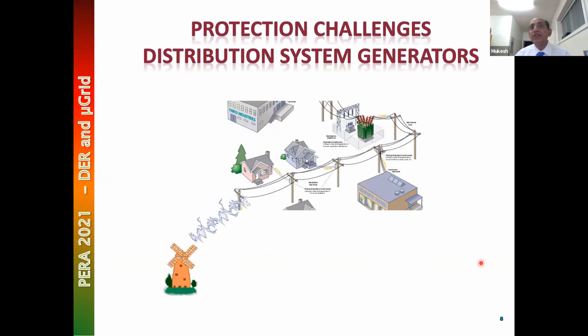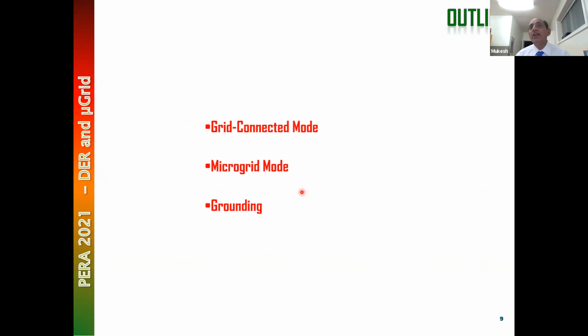So we have a distributed generation connected to a distribution system, and what kind of things is it going to do? First, we will talk about what kind of problems are introduced by connecting a generation to a distribution system which is designed for a unidirectional power flow. And we will talk about it assuming this source is going to be connected only when it is running in parallel with the utility system. That means the small source running in parallel, what kind of problems it can create. Then we'll go to the next step. If it is running separated from the system, allowed to form a microgrid, what kind of problems will arise. And a very important thing in this is grounding.